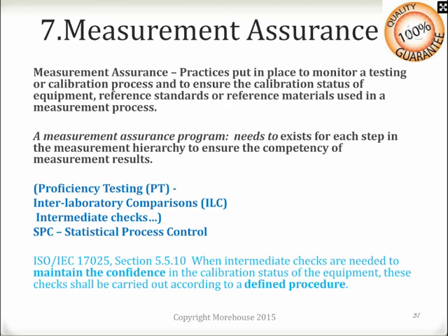Okay, so how do I ensure I'm making the proper measurements? I alluded to this earlier with proficiency testing. There are several service providers out there offering this service. Interlaboratory comparisons, ILC. You can check En ratios. This is on the sheet. If you send us an email and ask for a copy of that spreadsheet, we'll gladly give it to you.